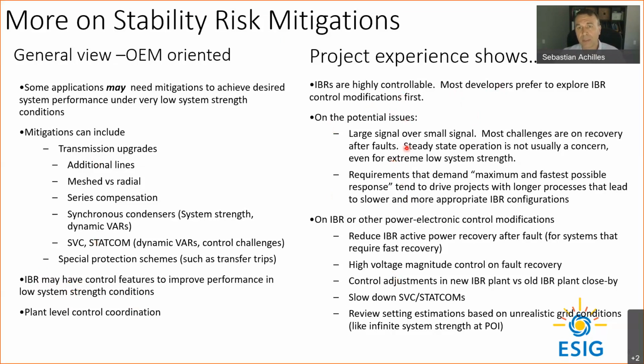Potential issues that we see, so the problems, as I mentioned before, are typically related to fault behavior. If we were to look at small signal and large signal perturbations, the small signal perturbations with weak grid are typically resolved in the industry by now. So most inverter-based resources are small signal stable, even in very weak grid conditions. The challenges are more related to surviving faults, and the recovery after the fault.